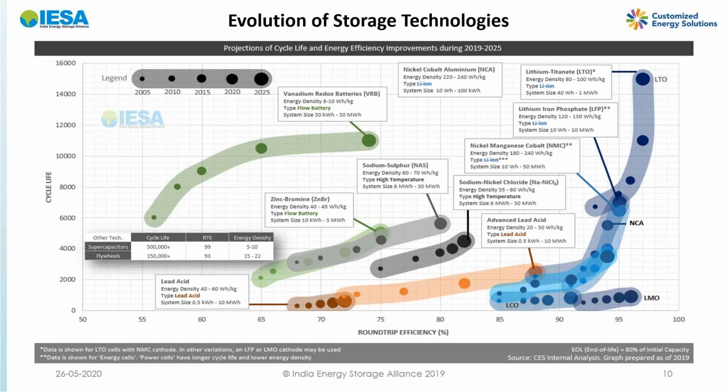Typically for most energy applications, we see anywhere from 3,000 to maybe 6,000 cycles as a very good number, because when you're using the system once per day, you're looking at 300 to 350 cycles in any given year. So even with 5,000 or 6,000 cycles, you can get more than 15 years of life. Although electrochemically the chemistries can work, in terms of the construction and packaging at the cell level, the warranties are typically 10 years.